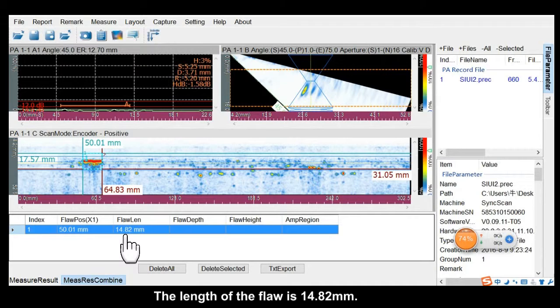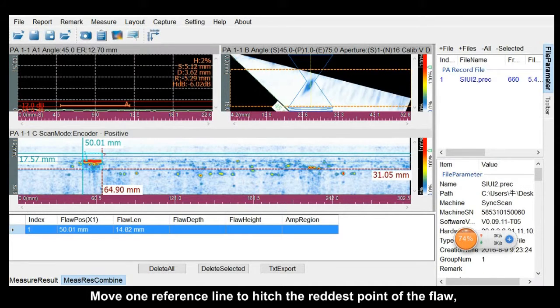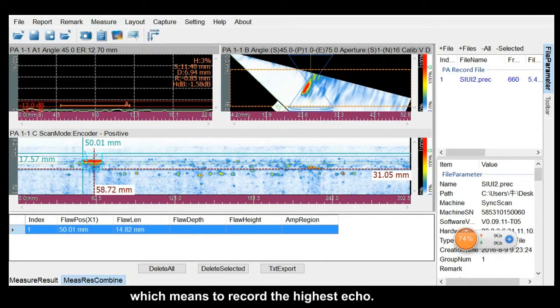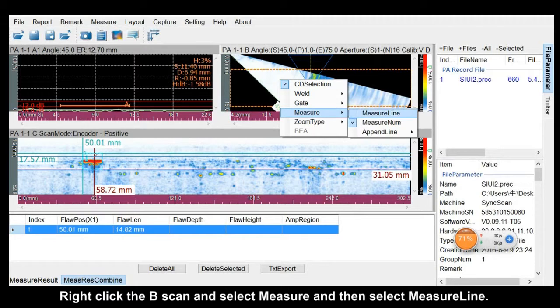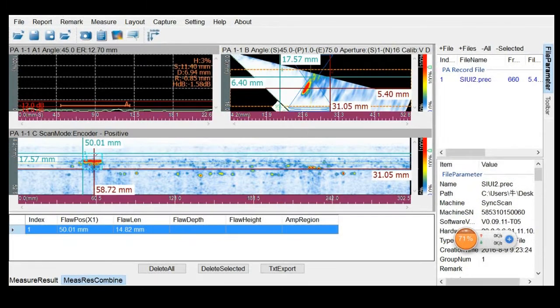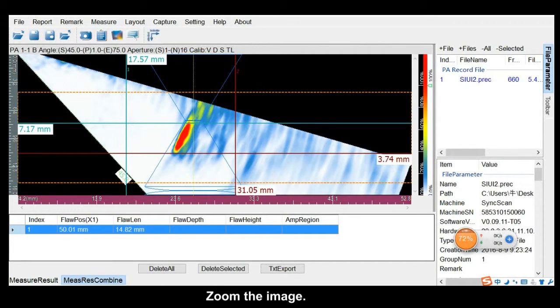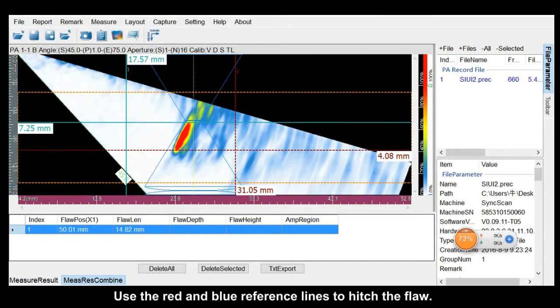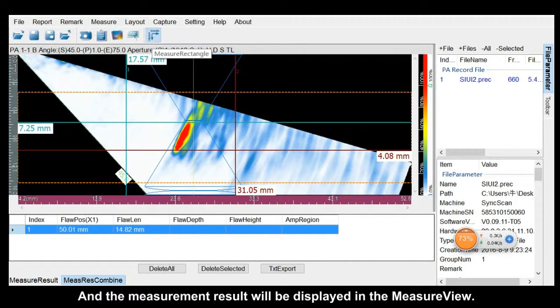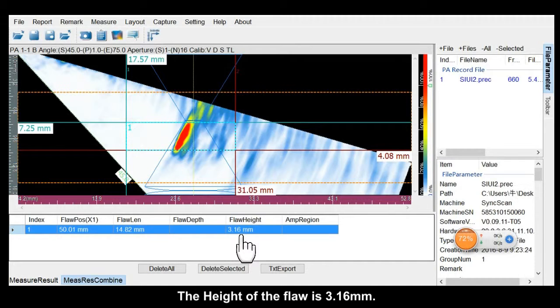The length of the flaw is 14.82 mm. Move one reference line to record the radius point of the flaw, which means to record the highest echo. Right-click B-scan and select Measure, and then select Measure line. Zoom the image. Use the red and blue reference line to record the floor. Click Measure Rectangle, and the measurement result will be displayed in the measure view. The height of the flaw is 3.16 mm.